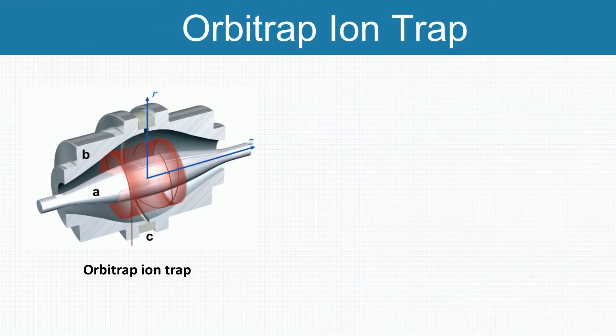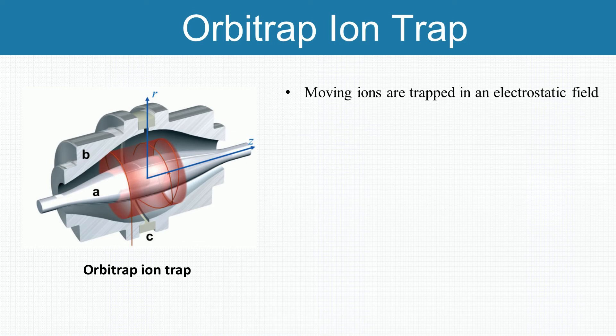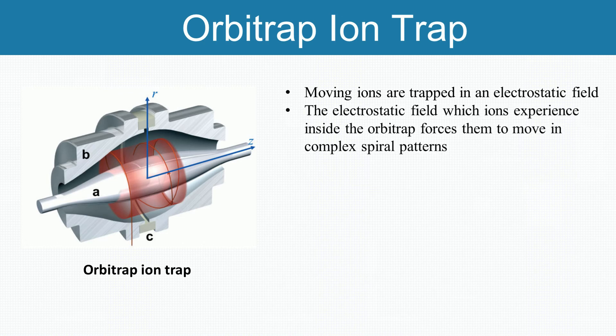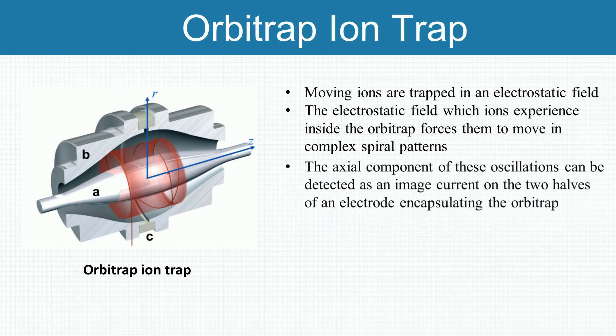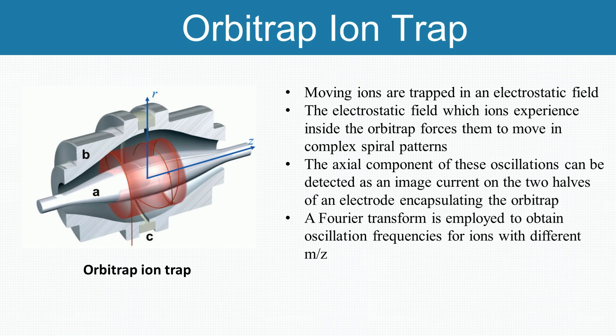Orbitrap is the newest high-resolution mass analyzer. In orbitrap, moving ions are trapped in an electrostatic field. The electrostatic attraction towards the central electrode is compensated by a centrifugal force that arises from the initial tangential velocity of ions. The electrostatic field which ions experience inside the orbitrap forces them to move in complex spiral patterns. The axial component of these oscillations can be detected as an image current on the two halves of an electrode encapsulating the orbitrap. A Fourier transform is employed to obtain oscillation frequencies for ions with different masses, resulting in an accurate reading of their mass-to-charge values.